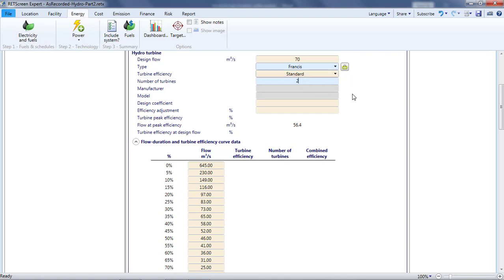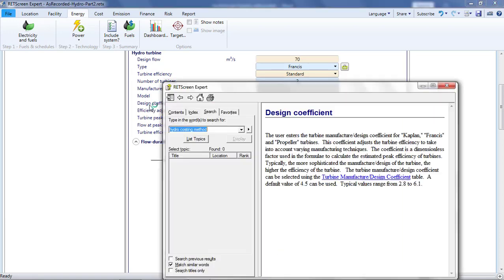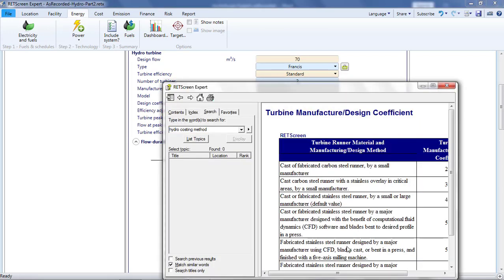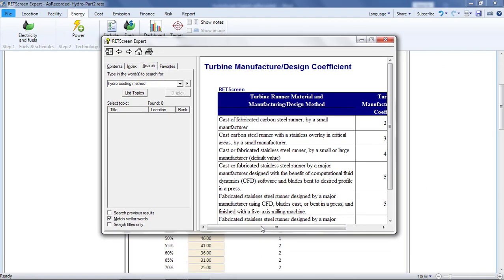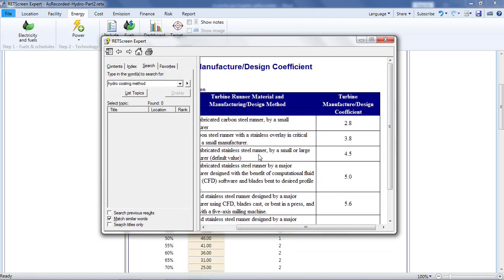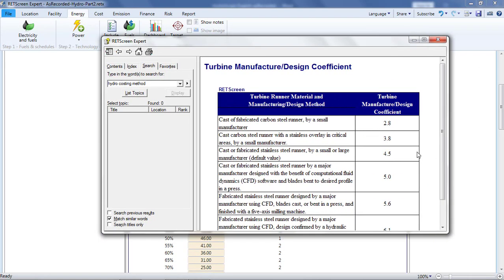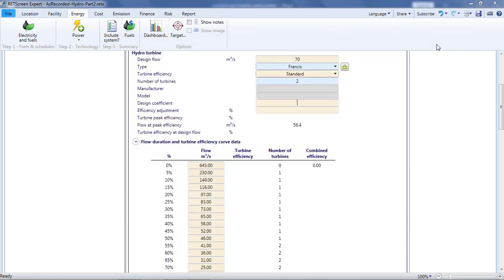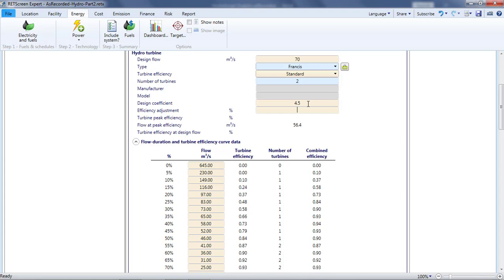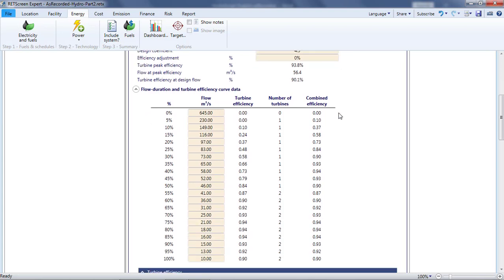I enter 2 for the number of turbines. For the design coefficient, I look at the help. It tells me that this parameter adjusts the turbine efficiencies to reflect the quality of manufacturing. I don't have information about this, so I'll use the default value of 4.5. Now I can see the results in the table below. The Turbine Efficiency column shows the efficiency of a single turbine for flows varying between 0 and 100% of that single turbine's design flow rate. In our case, the design flow rate for a single turbine is the project design flow rate of 70 cubic meters per second divided by 2, the number of turbines.